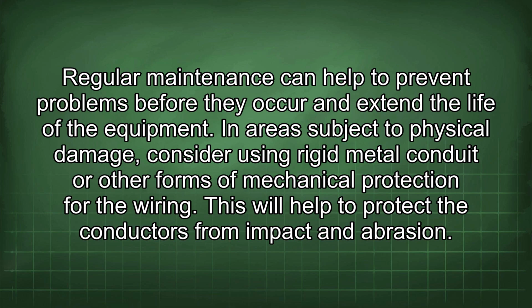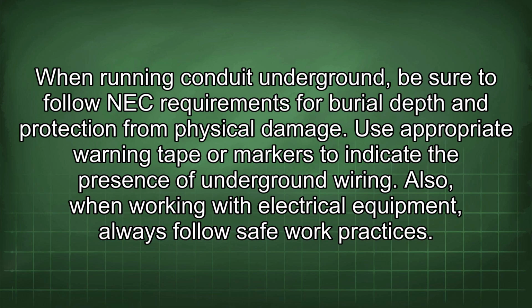In areas subject to physical damage, consider using rigid metal conduit or other forms of mechanical protection for the wiring. This will help to protect the conductors from impact and abrasion. When running conduit underground, be sure to follow NEC requirements for burial depth and protection from physical damage. Use appropriate warning tape or markers to indicate the presence of underground wiring.